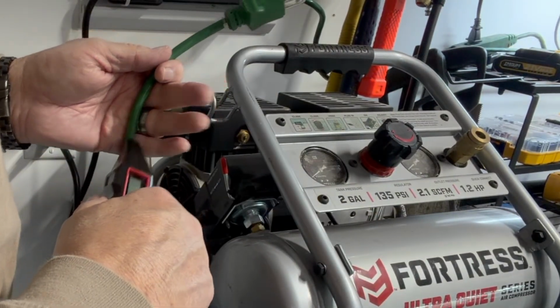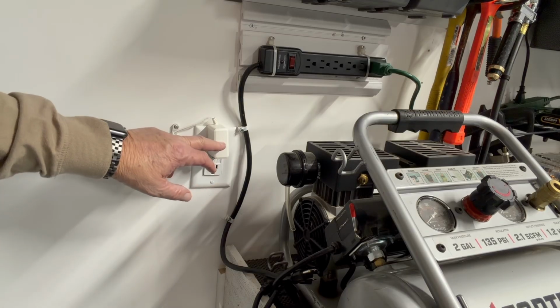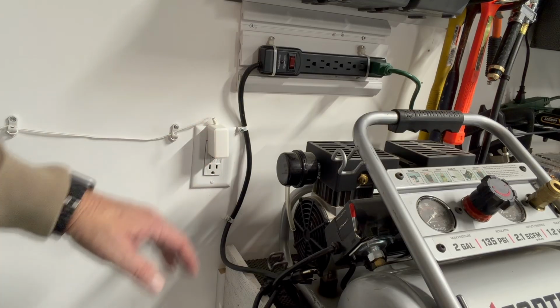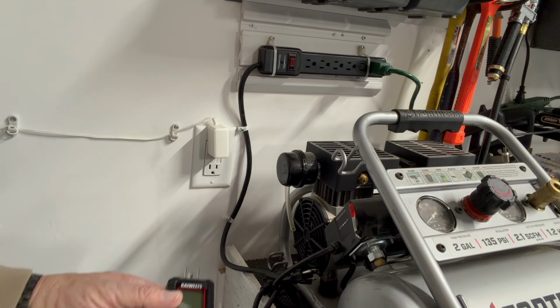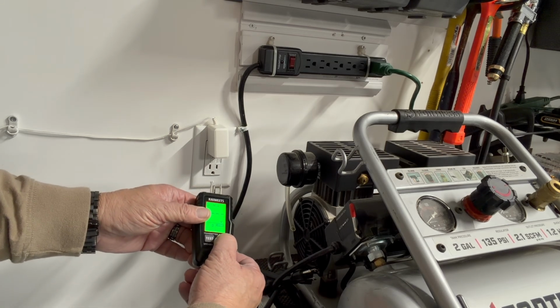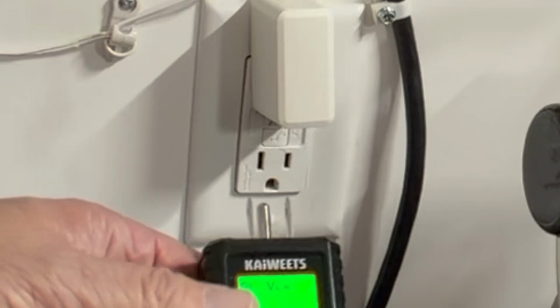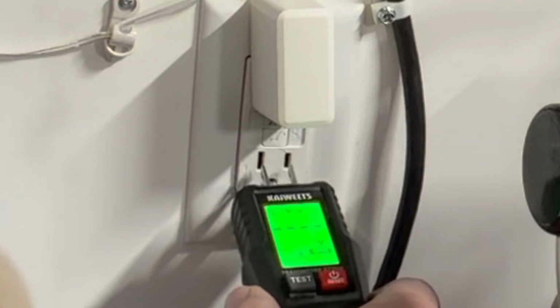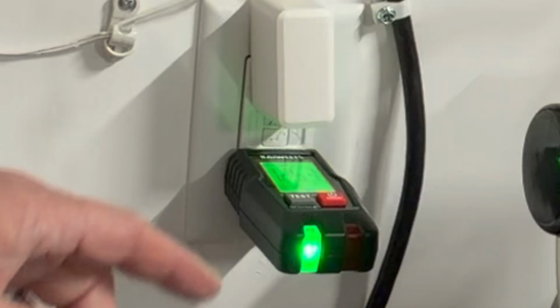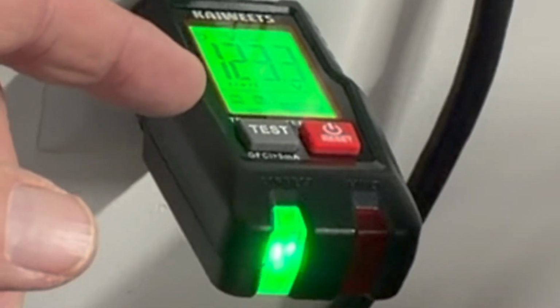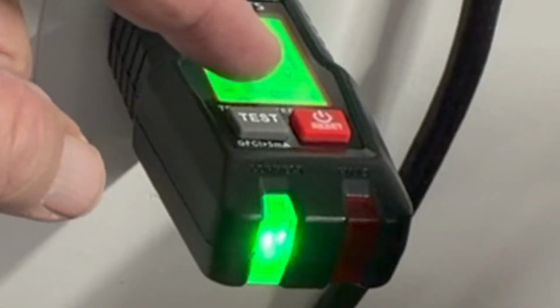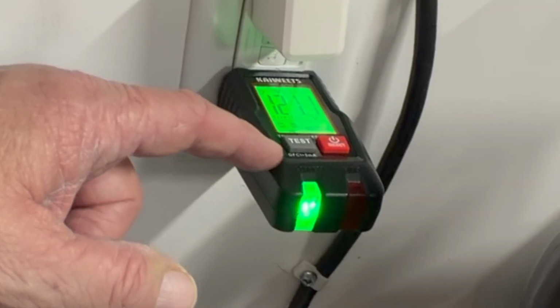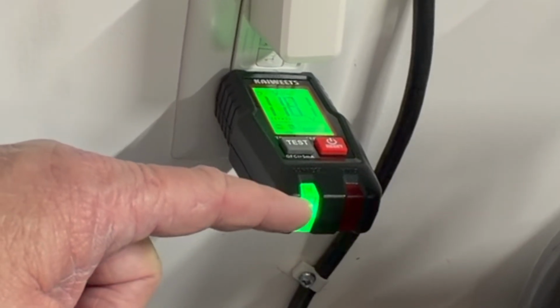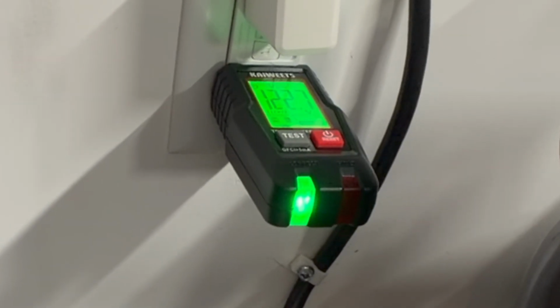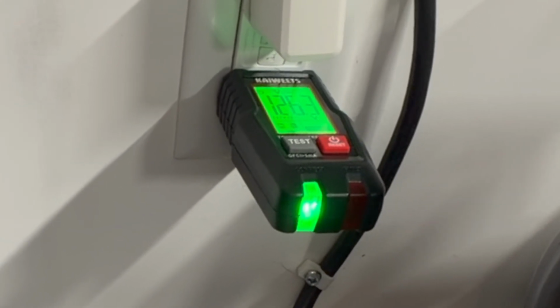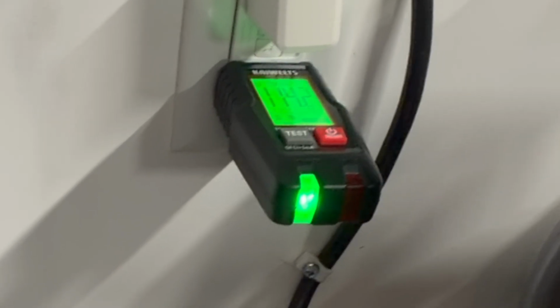No voltage. Okay, this is a ground fault plug, and I have my internet router plugged into that, so I don't want to unplug it. But another way to test it, you could turn this on. There's no voltage or anything indicated until you plug it in. Hopefully you can see it indicates 120 volts. It says it's correct on this side. And then the green indicator that's solid indicates that the wiring is correct.